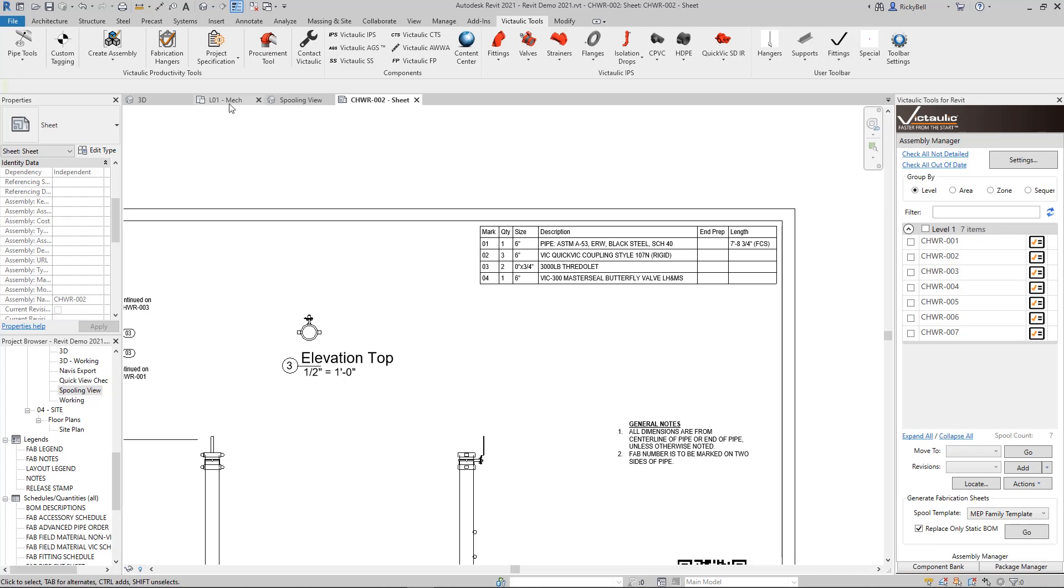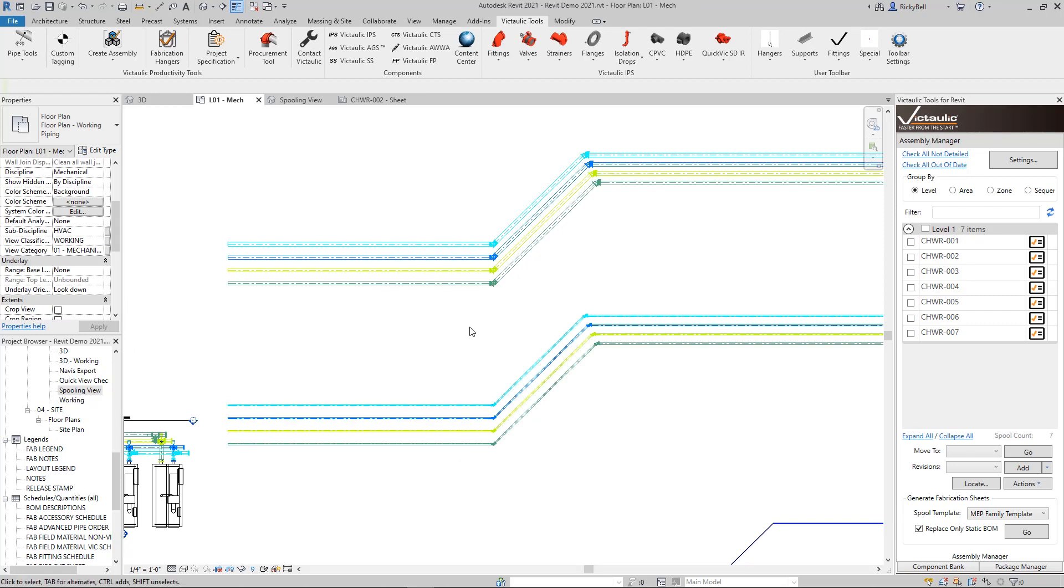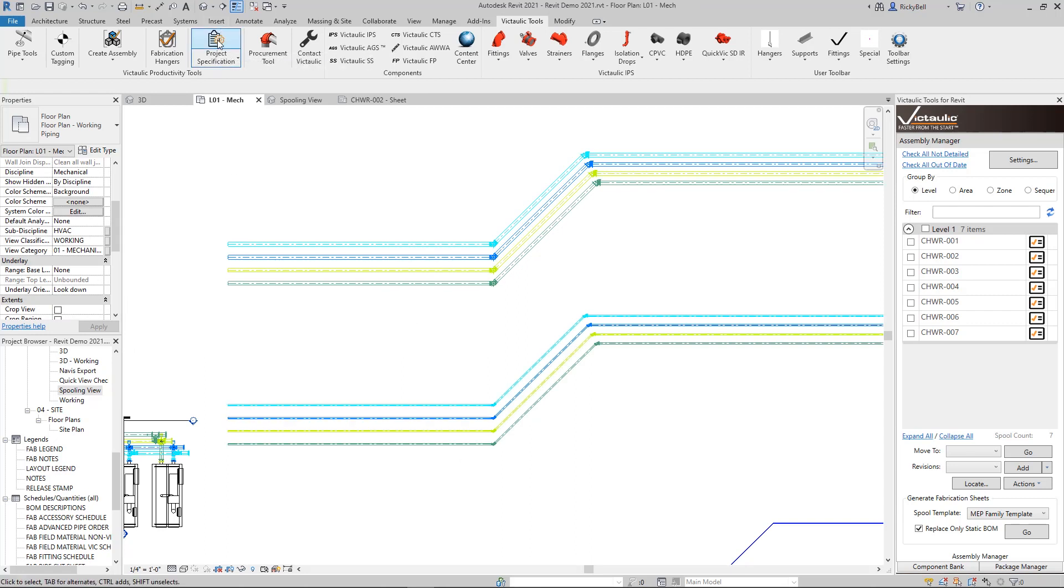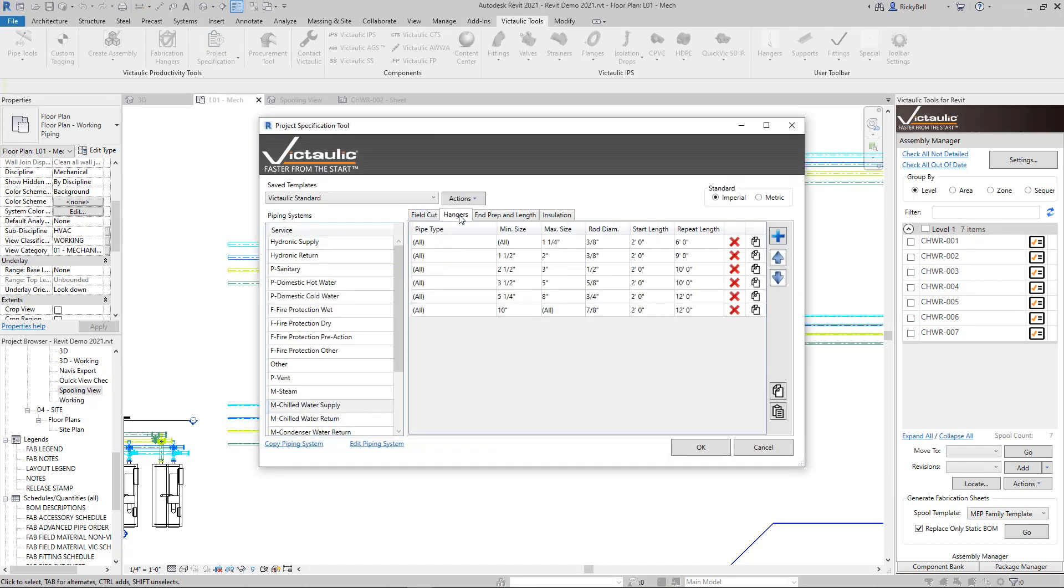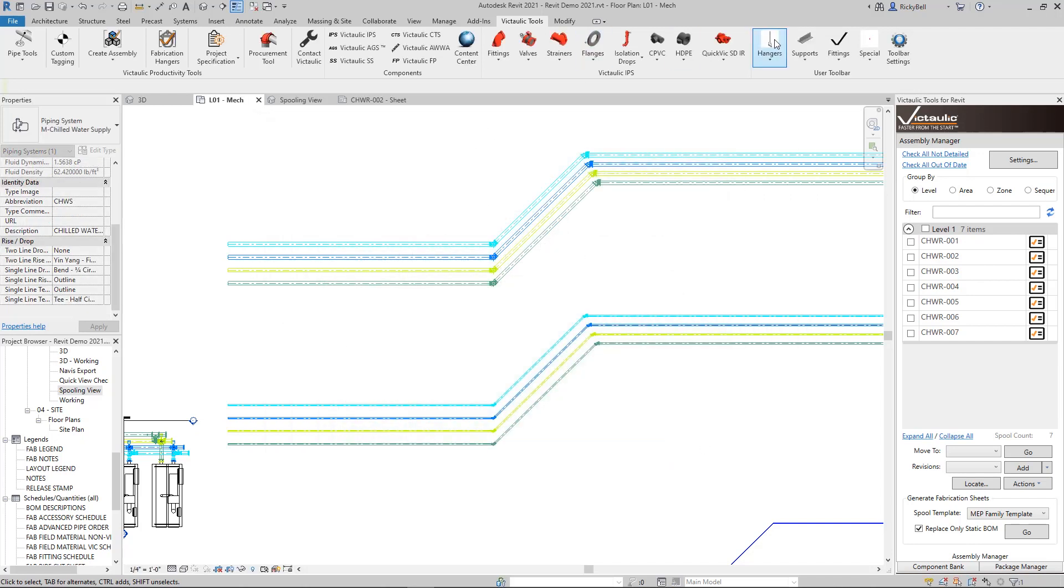So the project specification tool can also assist in placing hangers and determining the hanger distances. Over here I have a plan view. I have the four piping system set up right here in 10 inch, and I have the same four set up here in 4 inch. If I go back to my project specification rules for chilled water supply and hangers, I'll see that 4 inch should fall at a 10 foot repeating distance and everything above that gets 12.